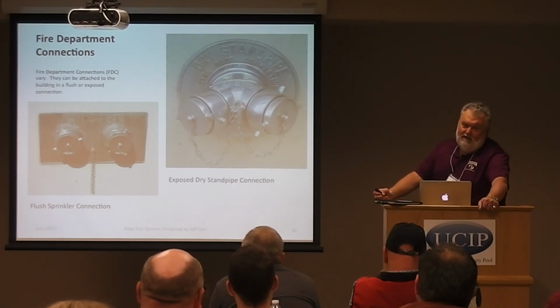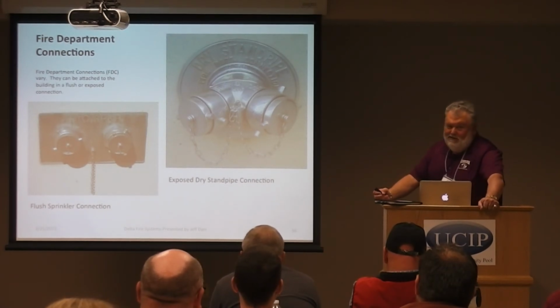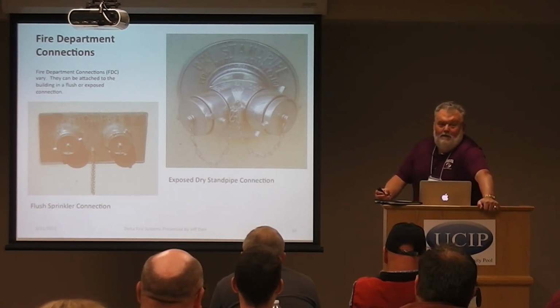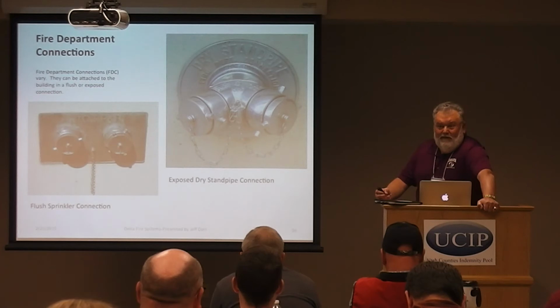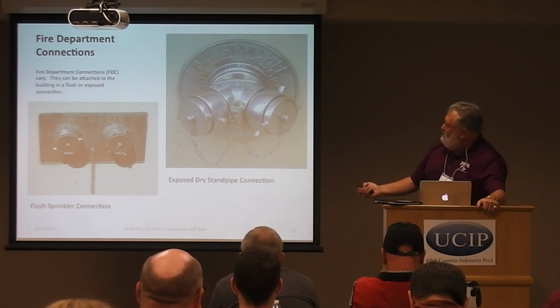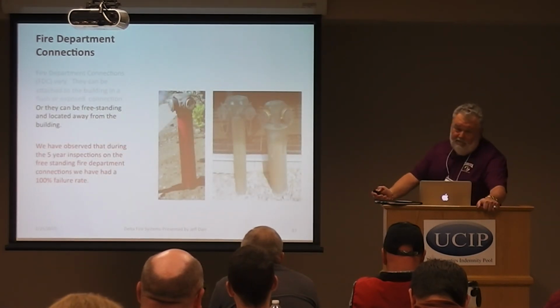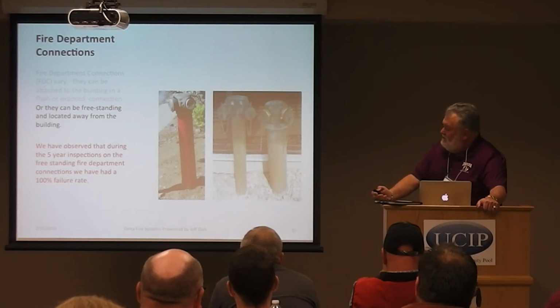One of the things we find as problems is most of these are made out of brass, and we find that people steal these caps and everything else and sell them. We've even found that they actually cut the fire department connection right off the wall and take the whole connection, not just the caps. So, by all means, look at those on a weekly basis. Here are some freestanding fire department connections.